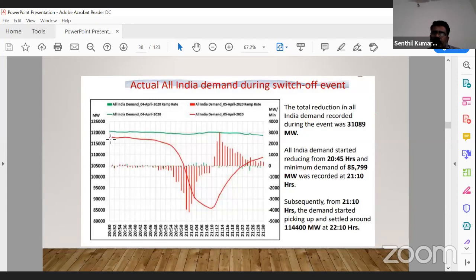Preliminarily, we took a lot of action. What actions did we take? We controlled the voltage, controlled the frequency, and controlled generation and demand. Based on the demand, you have to maintain the generation. When demand suddenly crashed, we reduced our conventional generation and quickly picked up hydro generation as reserve power. Reserve powers like hydro power and gas power plants were maintained, and nuclear power was also fully maintained in its generation.